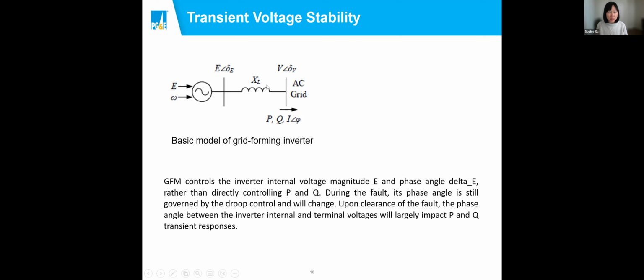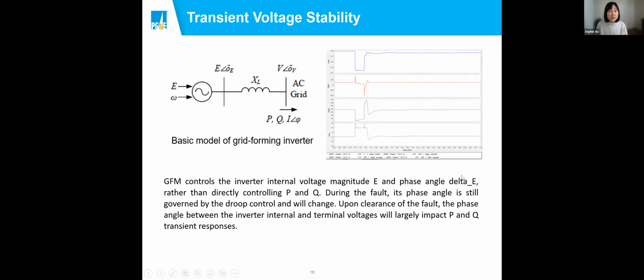But for grid forming inverter, if you don't have additional controls on top of it, the P and Q output is really the natural response from the internal voltage, the phase angle, and its magnitude. And here is just a general, very quick test of what you will see if you have a grid forming inverter responding to a system fault. The top is the voltage, the second one in red is the reactive response, and the third is the real power response.